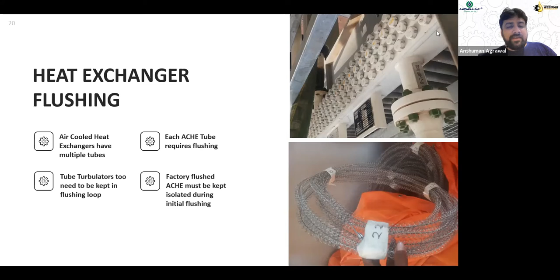The second interesting fact we found at the site was that the loops or the tubes of heat exchangers have certain turbulators. These are called tube turbulators, for increasing the efficiency of the heat exchanger. But when you do the flushing, these turbulators need to be handled very delicately because they are like mesh, they are like a net. And when you perform the flushing, they start trapping the debris inside the turbulator wires. And this debris which gets trapped in the turbulator wires starts getting released when you close or conclude your flushing. So you need to perform the flushing without the turbulators. Then you again need to perform the flushing with the turbulators before you hand over the system for commissioning. So turbulators need to be handled very cautiously whenever you find them in the tubes of the heat exchangers.